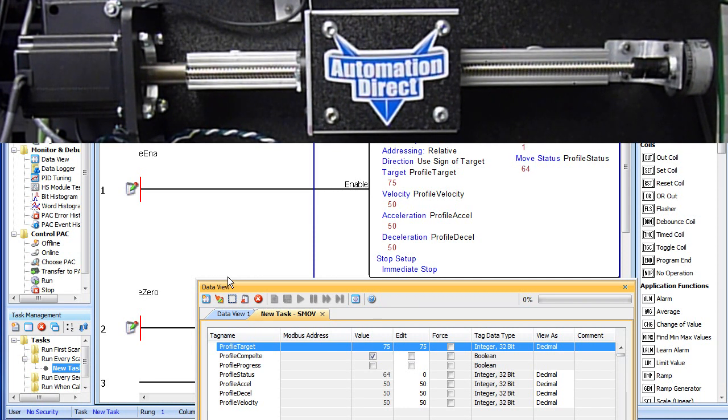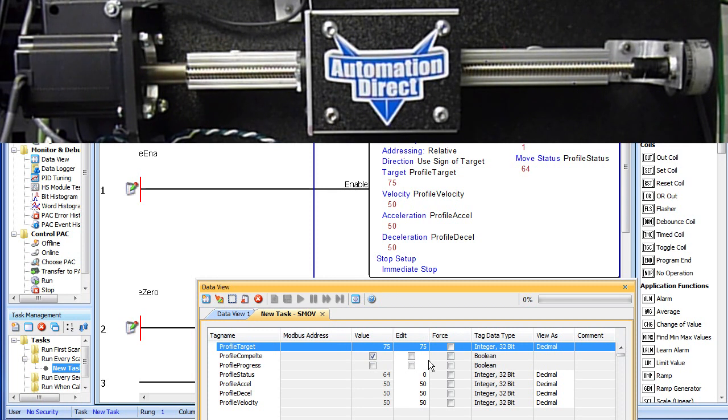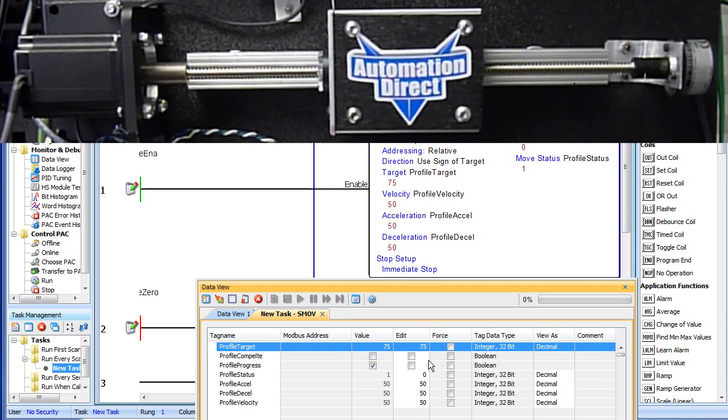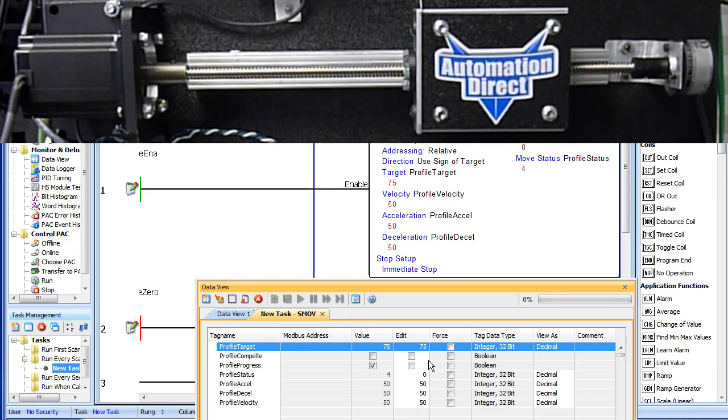Now, if I enable the carriage again, it will move another 75mm because this is a relative move. It's going to move 75mm from where I currently am. If this was at an absolute move, it would just stay where it was because I am already at 75mm. So let's try it. I'll flip the switch and sure enough it moves another 75mm.